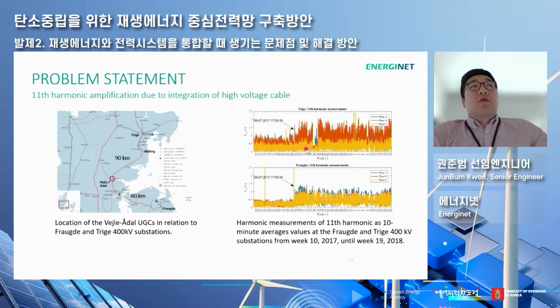And when they synchronize with the 11th harmonic and 10th harmonic, it's going to create a lot of amplification. It's the TSO's responsibility to analyze this precisely so that they have an accurate understanding of what kind of ripple effects this will have down the road. And in the eastern area, they have this 400 megawatt inverter. It's not shown in the PPT slides.